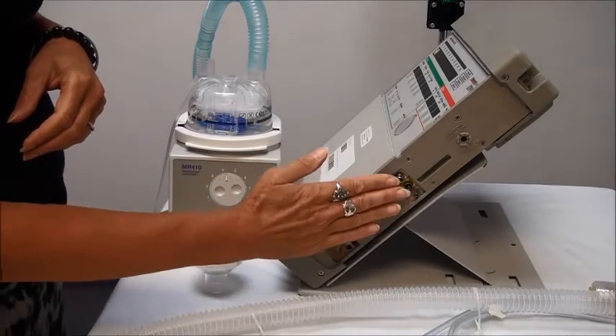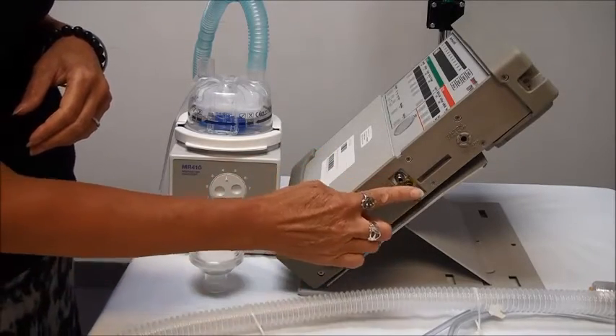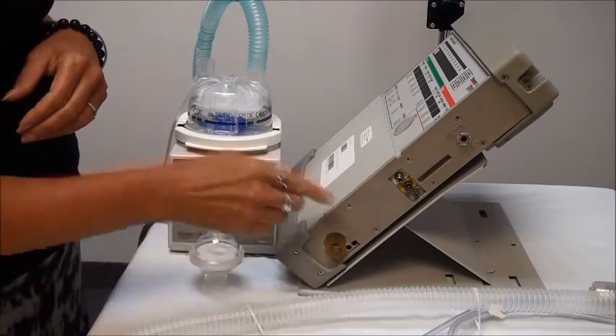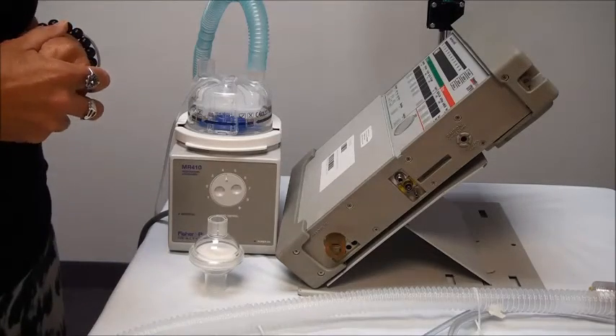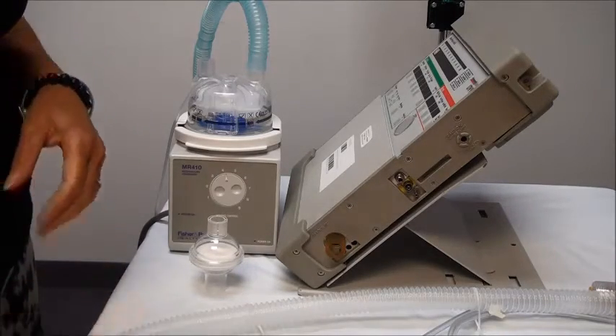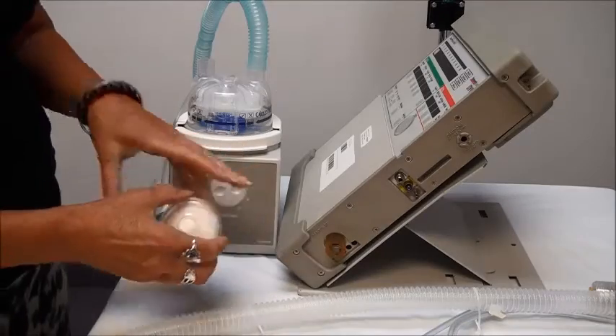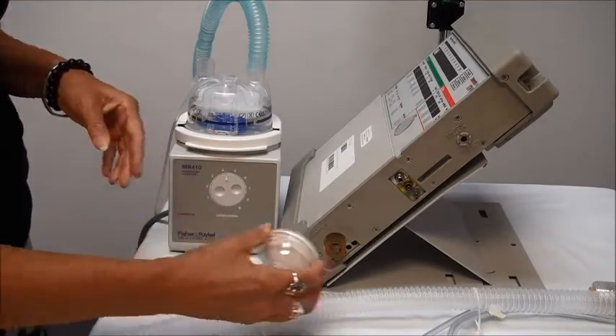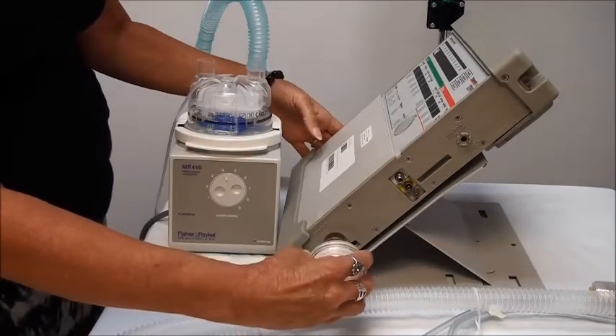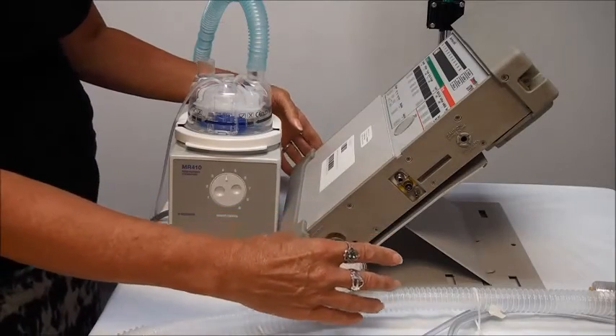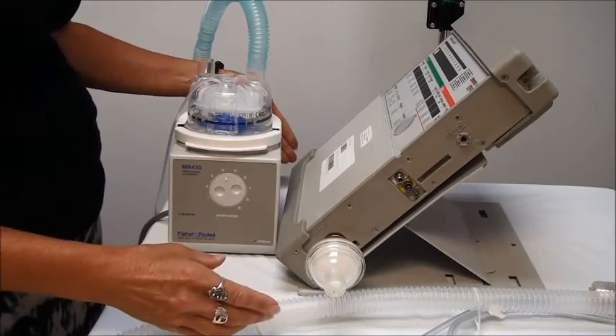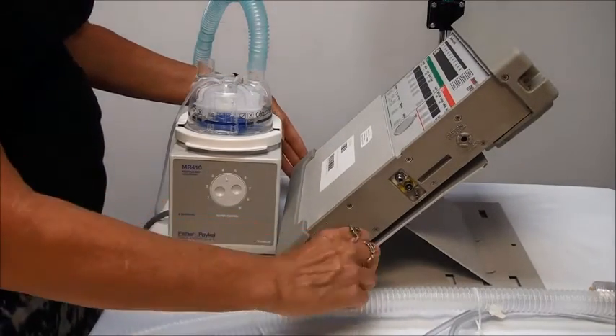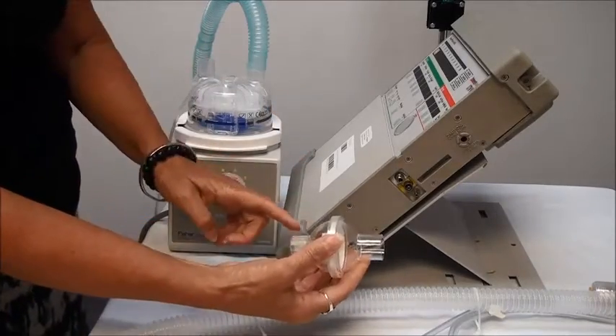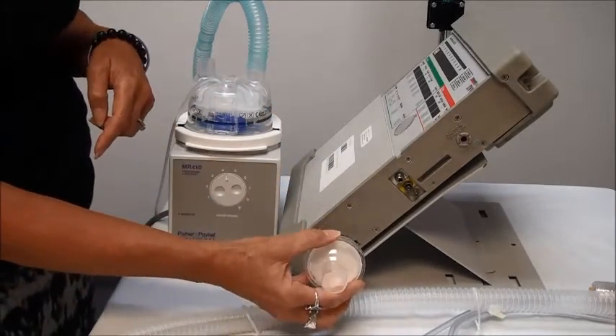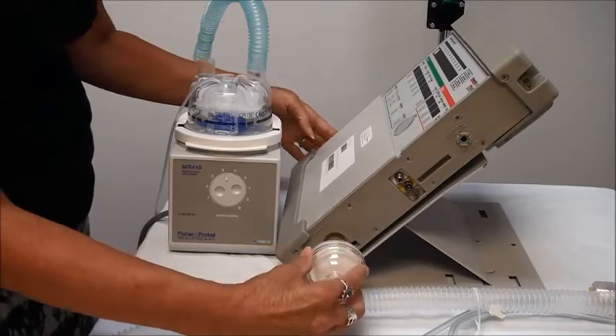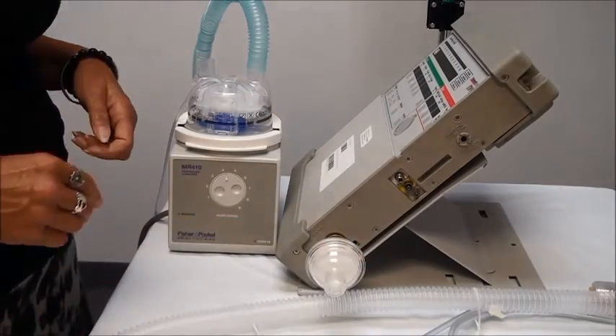Below that we have 3 small ports, and then 1 large port, and this is where your tubing is going to connect to. So on the bottom, I'm going to start there with the large port. This is where the air is going to come out that's going to ventilate your patient. And first we're going to put a bacteria filter on the ventilator. If you take a look, you can see that there's 2 openings. One is smaller, one is larger, and the larger end will fit right onto the ventilator.